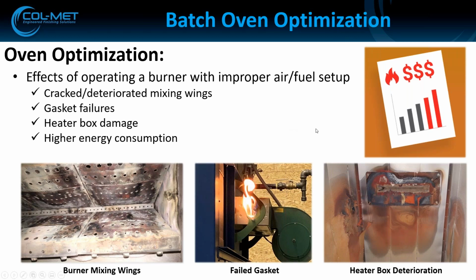So some of the first things you'd want to check is the combustion air, clean out the blower wheel, and you might even use a welding tip cleaner or something like that to clean out the holes in the mixing wings. But really the only way to know for sure what's going on is to connect a manometer to the test ports on the burner. And manometer sounds complicated and expensive, but it's not. It's just basically a pressure gauge that reads really low pressure. And we're talking less than 1 PSI.